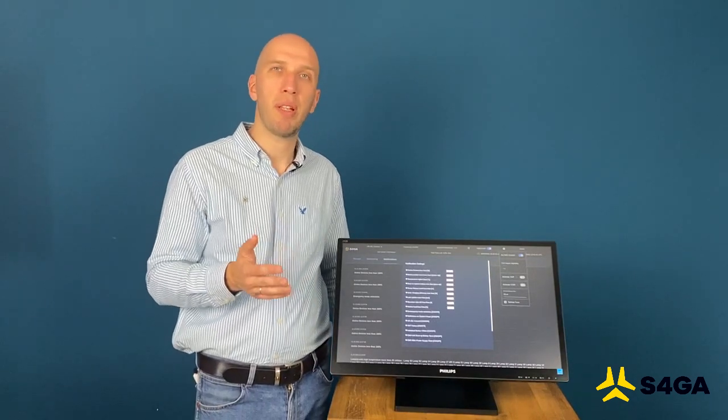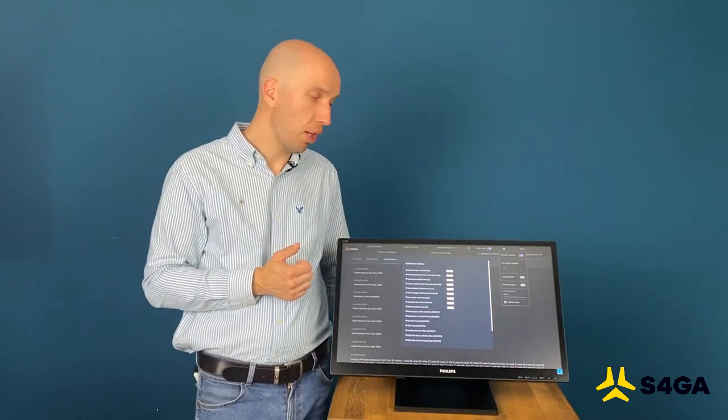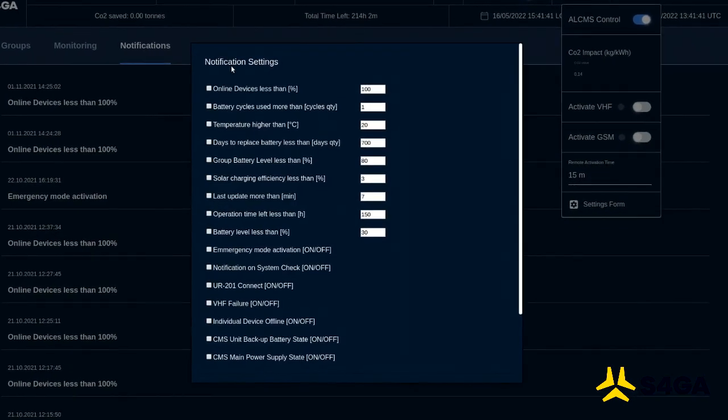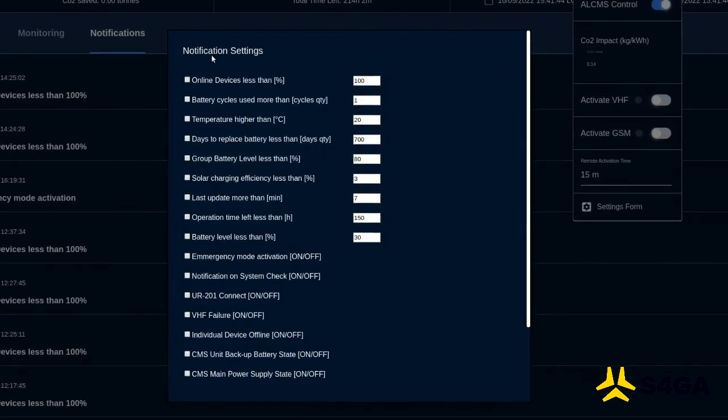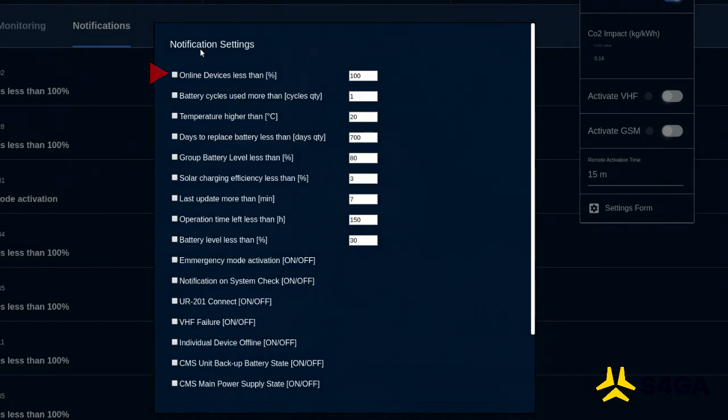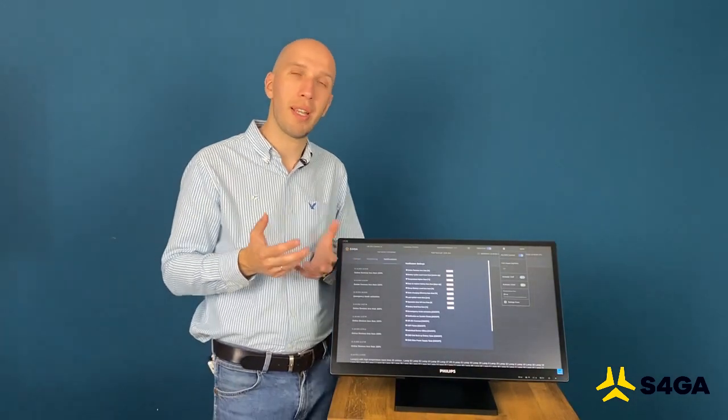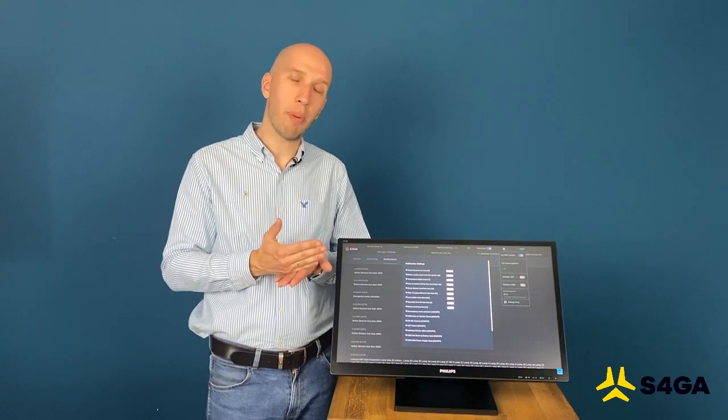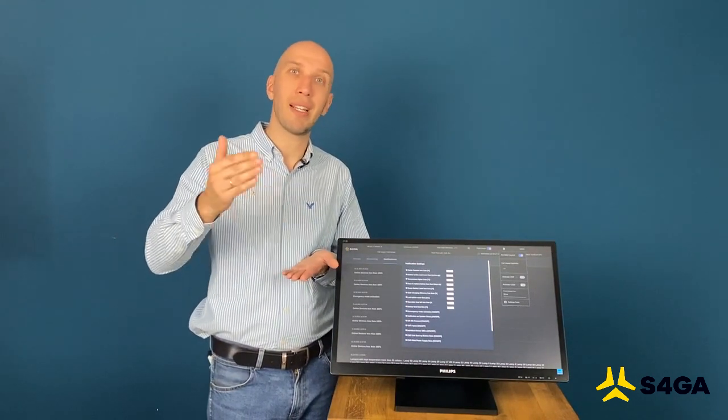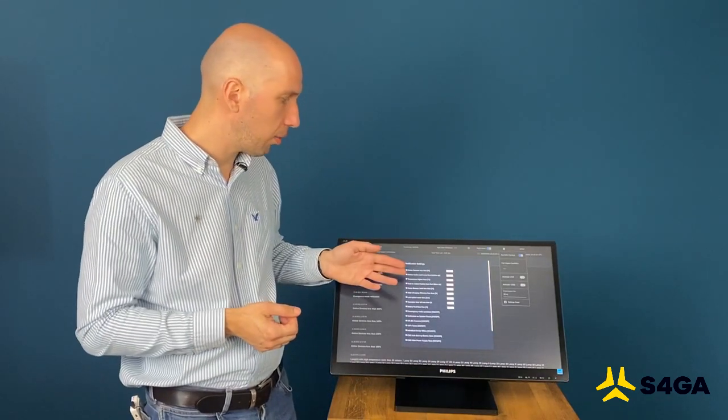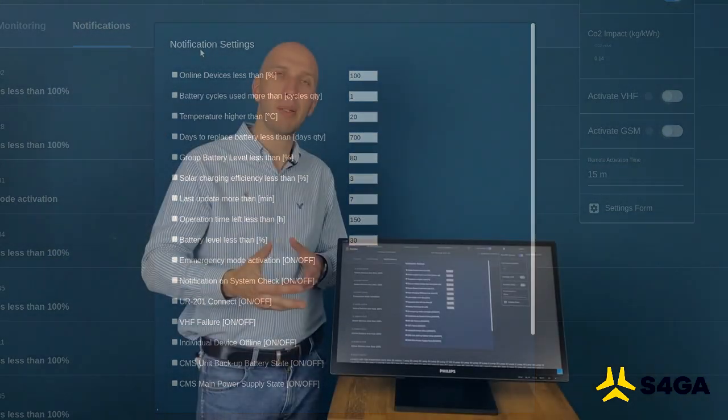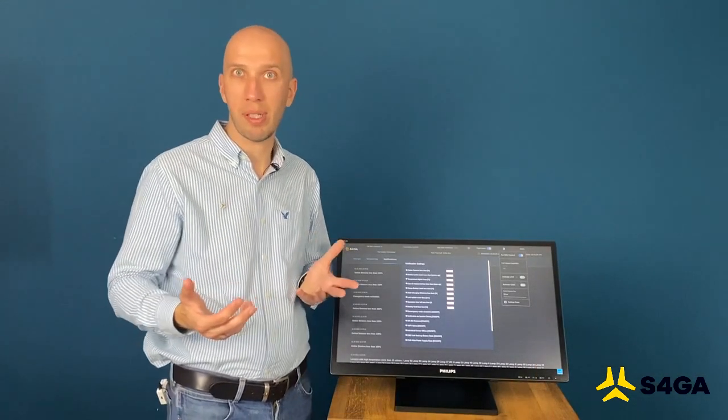Let me explain you briefly about thresholds for critical notifications. You have several parameters that you can yourself define. In my opinion, the most important ones here are number of online devices, which means that if you set up here 90%, then when amount of lights will be less than 90%, your system will notify you. As you know, there are certain regulations in ICAO or in EASA that requires you to abort operations when a number of your lights are less than X amount. Battery cycles used more than this is for the maintenance team to know when to exchange the battery, for example.